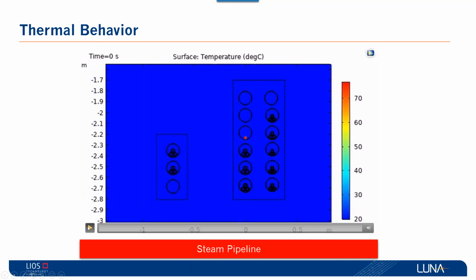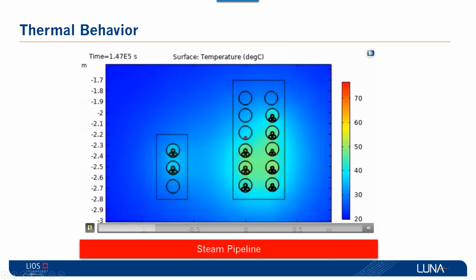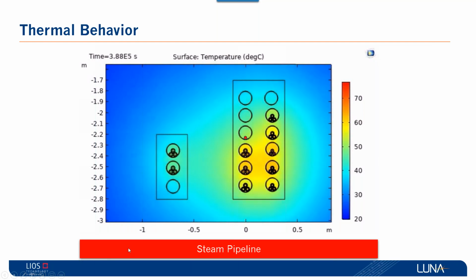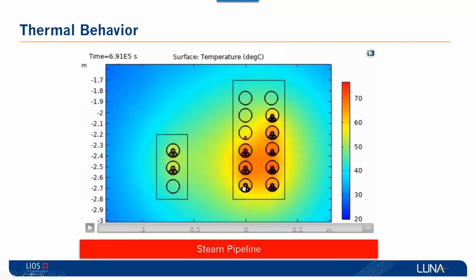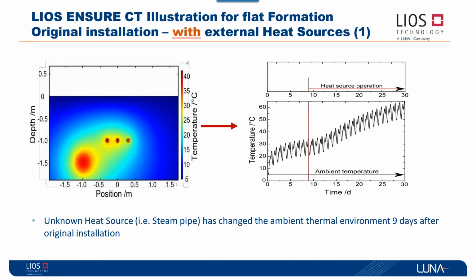Another case, which is exactly the case this time, is that you have the duct bank heating the same way, but at the same time you also have a steam pipe that's affecting you and heating this particular circuit. So in reality, when you think this circuit is seeing, let's say, 30 degrees Celsius, the steam line is affecting it, and the other surrounding circuits are also affecting the duct bank, including the circuit. So these are very challenging systems and algorithms to implement. But the beauty of the LIOS RTTR that we have is that it's a self-learning algorithm. As you can see, it can catch up, including when a heated external source shows up.